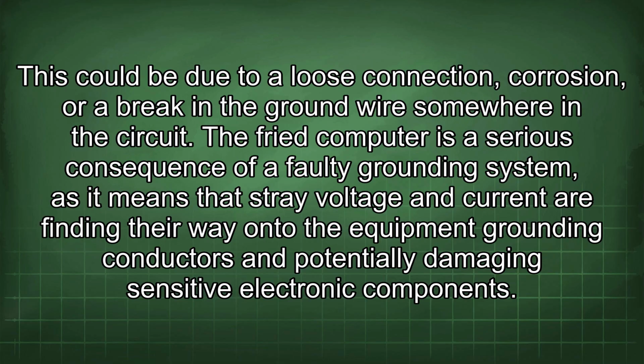The fried computer is a serious consequence of a faulty grounding system, as it means that stray voltage and current are finding their way onto the equipment grounding conductors and potentially damaging sensitive electronic components.